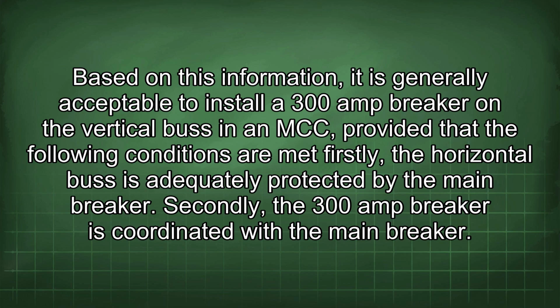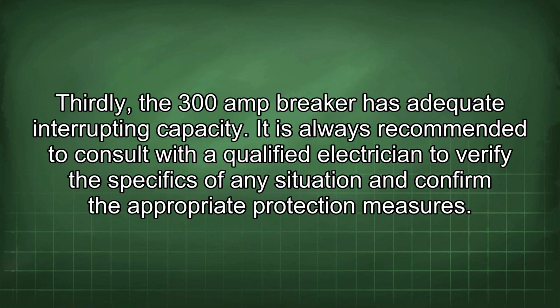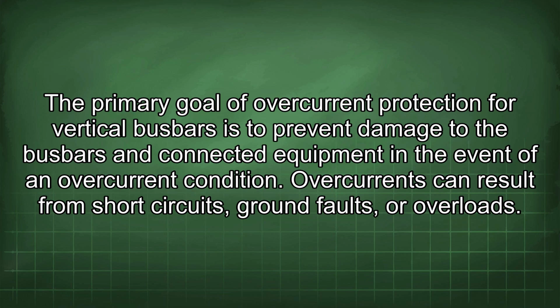Firstly, the horizontal bus is adequately protected by the main breaker. Secondly, the 300 amp breaker is coordinated with the main breaker. Thirdly, the 300 amp breaker has adequate interrupting capacity. It is always recommended to consult with a qualified electrician to verify the specifics of any situation and confirm the appropriate protection measures. The primary goal of overcurrent protection for vertical busbars is to prevent damage to the busbars and connected equipment in the event of an overcurrent condition.